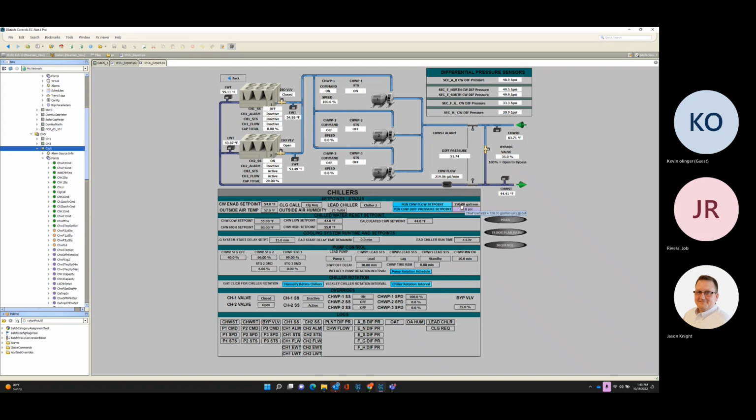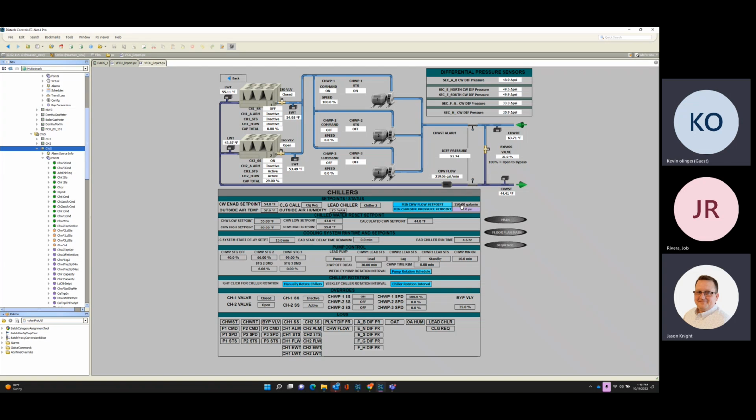And with the campus being as big as it is, during lower ambient conditions, like when it starts cooling off around 3, maybe 4, 4:30, 5 o'clock, especially over the last week, I've seen chill water valves all start to close down.